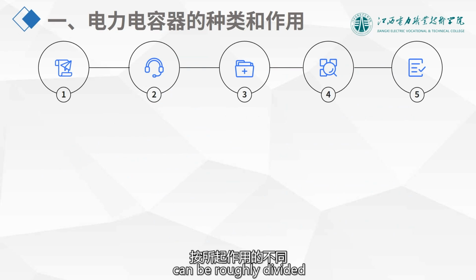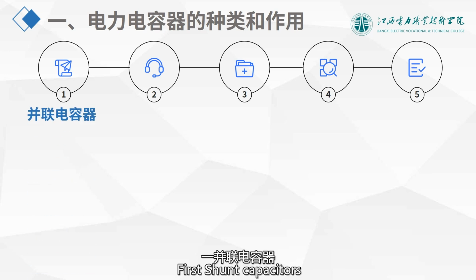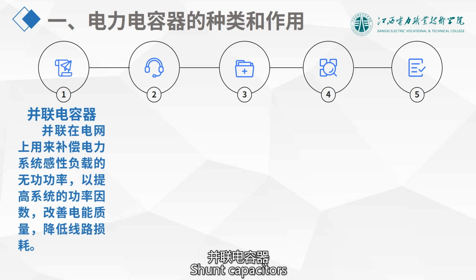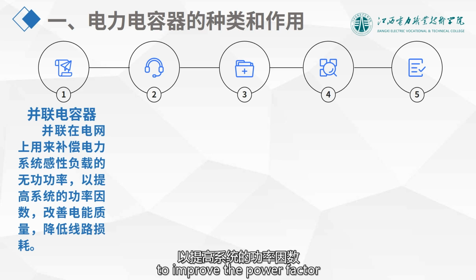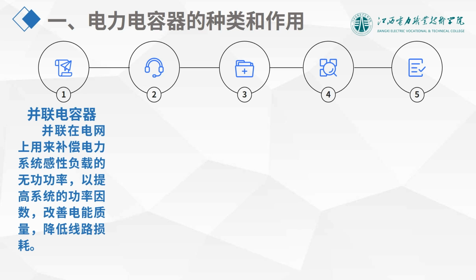Power capacitors can be roughly divided into 5 types based on their functions. First, shunt capacitors. Shunt capacitors are connected in parallel to the power grid to compensate for the reactive power of inductive loads in the power system to improve the power factor, enhance power quality, and reduce line losses.